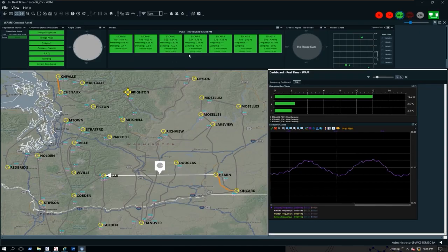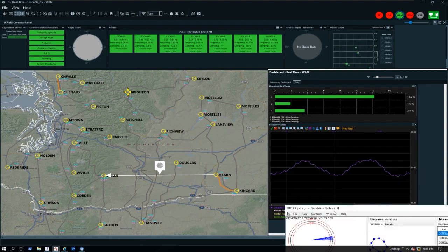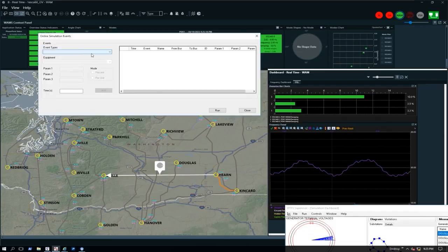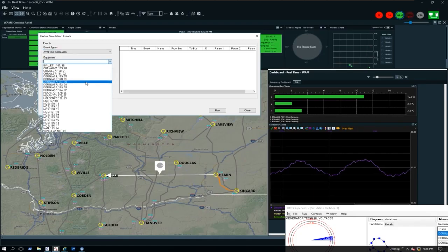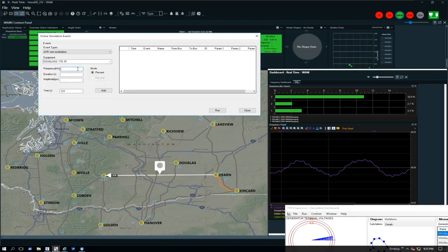But anytime it gets below 20%, we're going to start monitoring what that damping percentage is and then display it accordingly. So I've got a scenario that I'm going to start. At our Douglas substation, I'm going to put in a forced oscillation on the grid. So we've got our AVR sine modulation. I'm going to pick my Douglas unit 6. I'm going to put in a 1/2 of a Hertz frequency oscillation. I'm just going to make it for a short duration of 45 seconds.